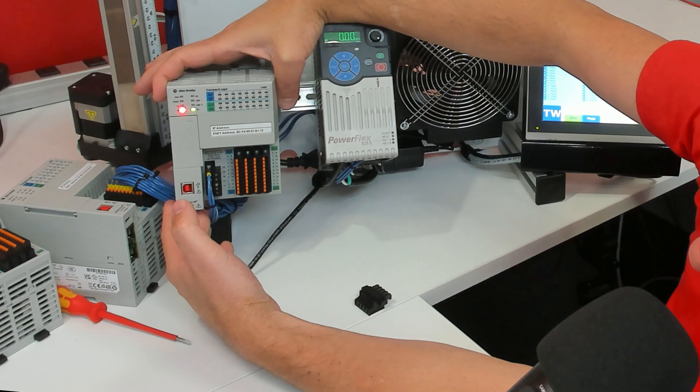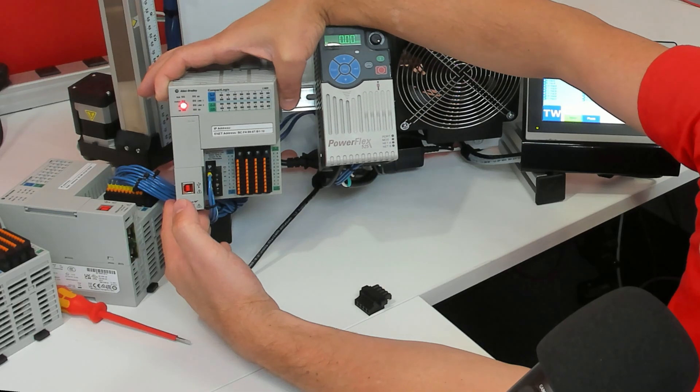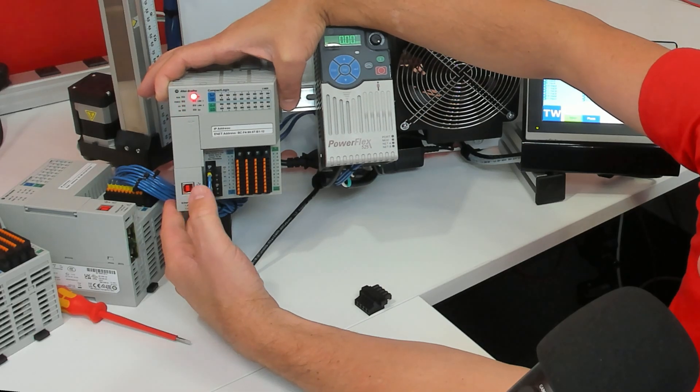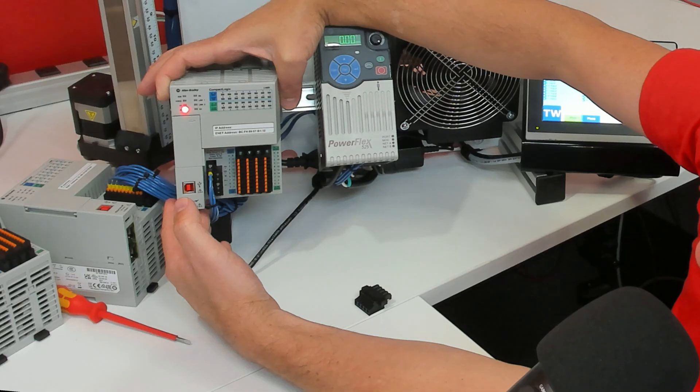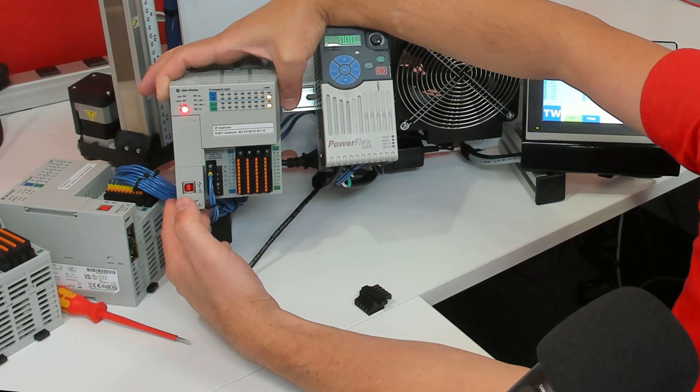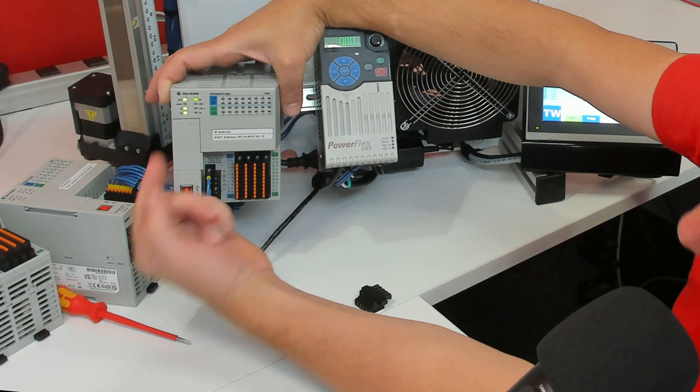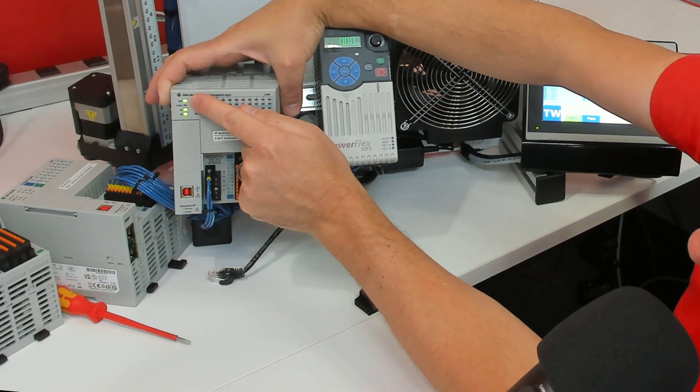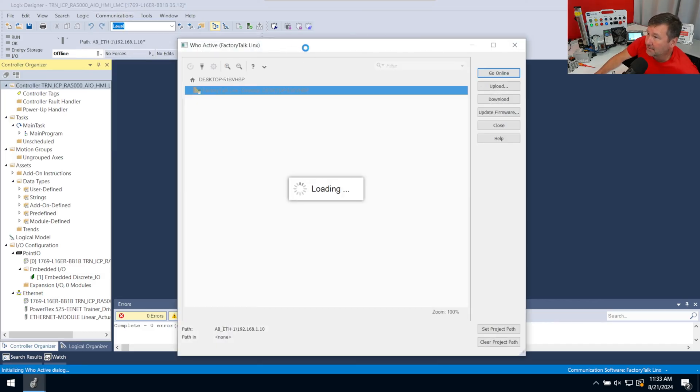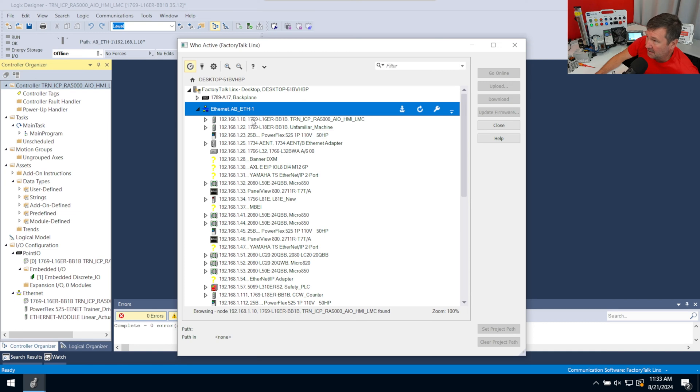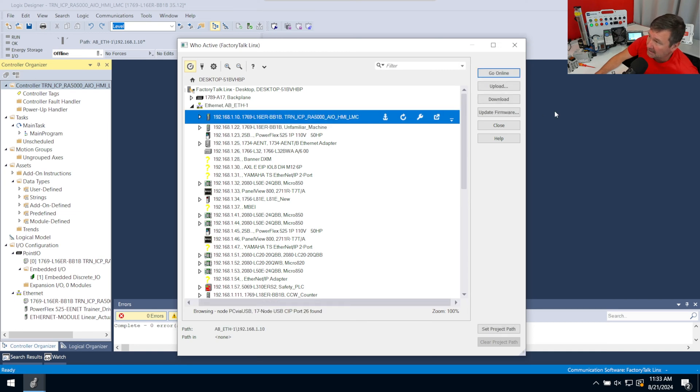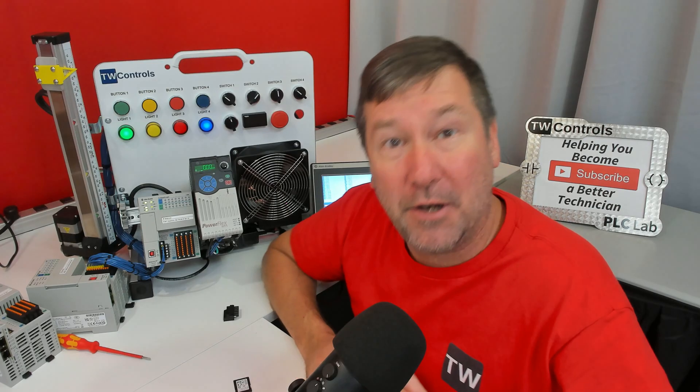Now it's going to do its typical power-up dance lights. And so now it is installing the firmware. Then it'll start going through its typical power-up checks. Loads the program from the SD card. Does its little dancing lights. And it's ready to go. So we have a solid green run light. And now if we go communications, who active, and open up our ethernet, in that one step of installing the SD, put the firmware on, assign the IP address, install this PLC program, and put it into run mode.